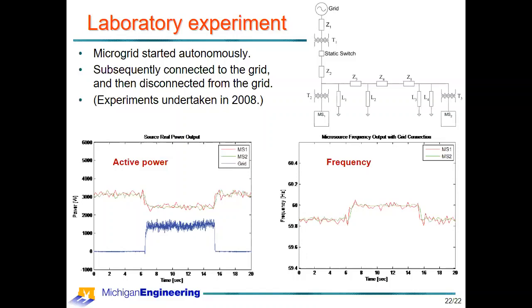This is a representation of a physical microgrid that we actually built in the lab. The starting condition is that the circuit breaker is open, so it's initially operating as an island microgrid, drawing that much power with no power drawn from the grid. Then at this point the circuit breaker closes, draws power from the grid, and the power supplied by the 2 inverter-based devices drops down. Here the breaker opens again and the grid power drops off.